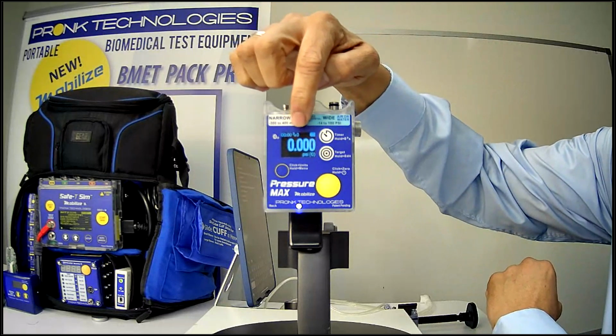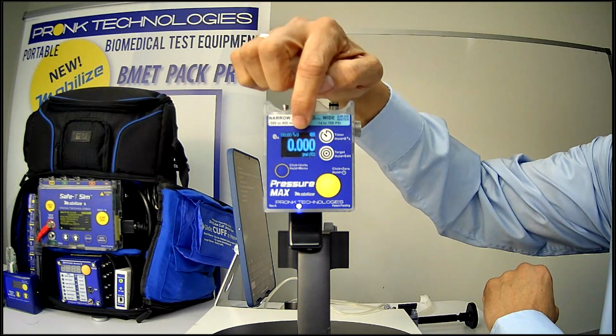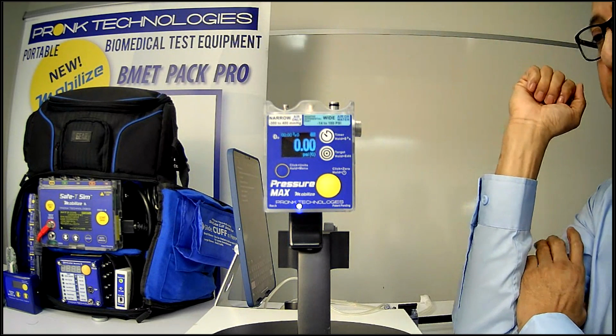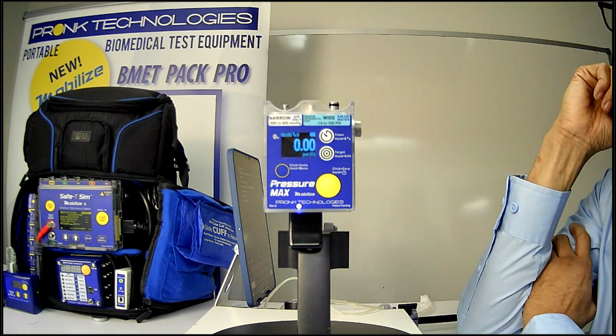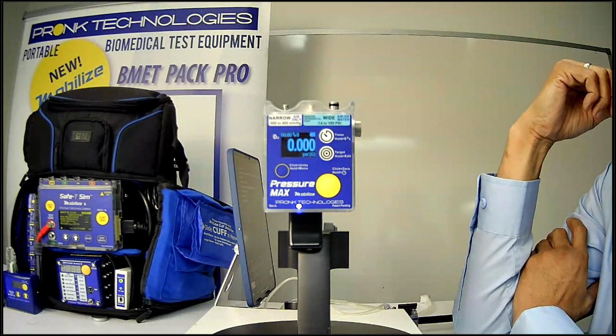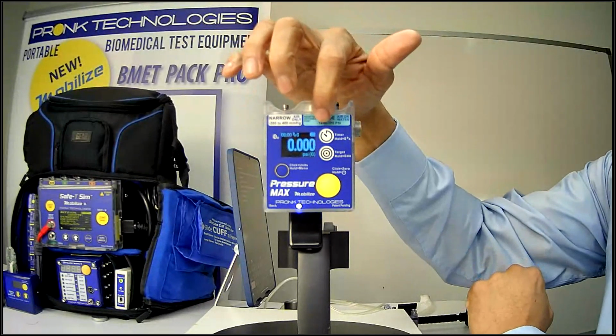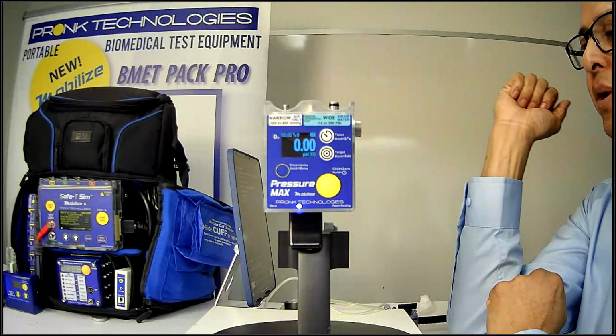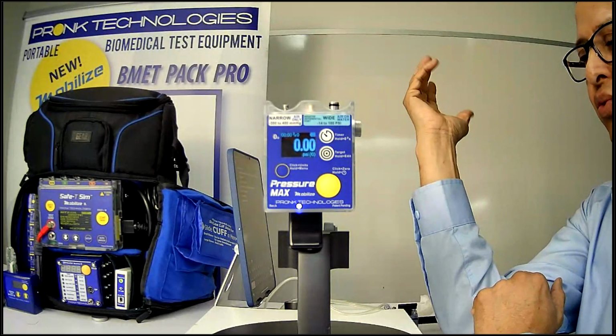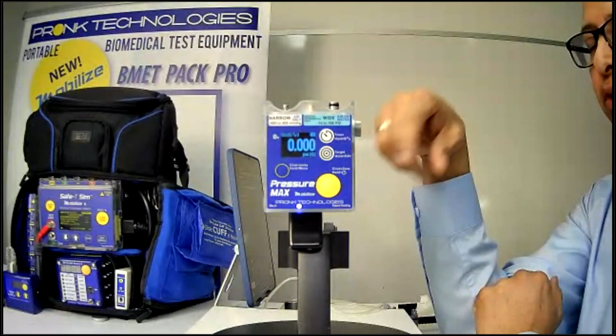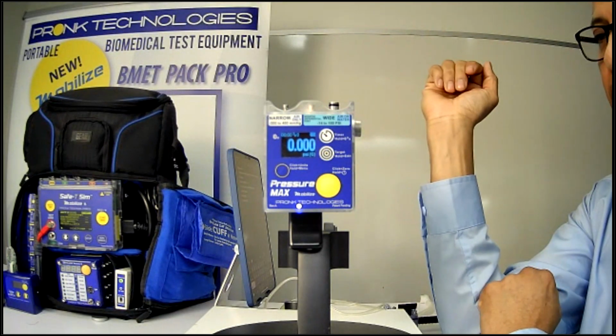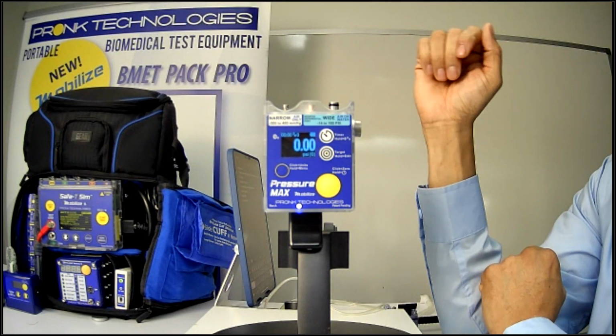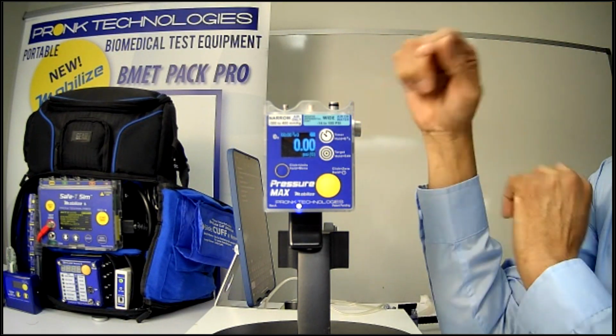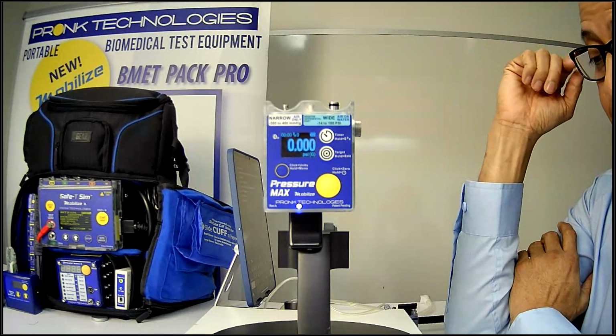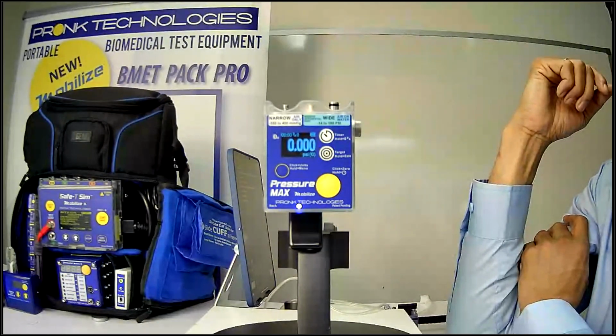In the center here, in the middle of the screen at the top, you're able to also capture peak pressure. So I'll demonstrate that for you in a moment. The unit can capture peak pressure. The top right is the power indicator. So if you're running on batteries or the external 6-volt DC power supply, it'll indicate to you what your power status happens to be. And then below that, you have your pressure measurement in units.